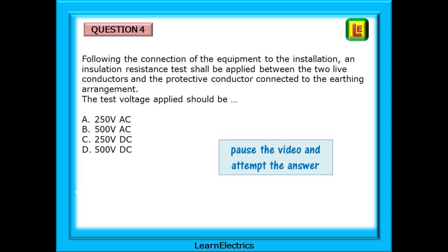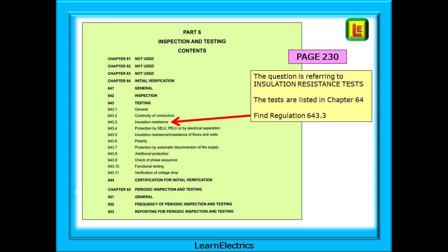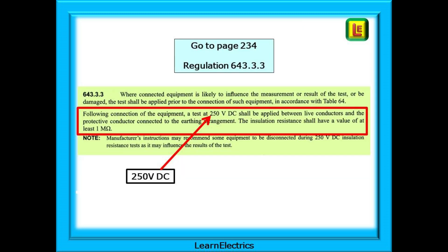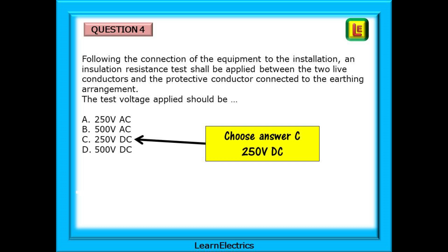Question 4: following the connection of equipment to the installation, an insulation resistance test shall be applied between the two live conductors and the protective conductor connected to the earthing arrangement. The test voltage applied should be — and four choices are given. Go to page 230 and find under chapter 64 the list of different tests. Regulation 643.3 is about insulation resistance tests. On page 234, Regulation 643.3.3 gives our answer: the test voltage to be applied is 250 volts DC — a popular exam setter choice. So our answer is C, 250 volts DC.